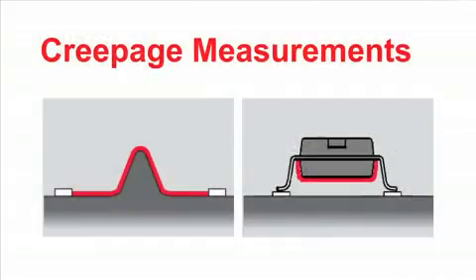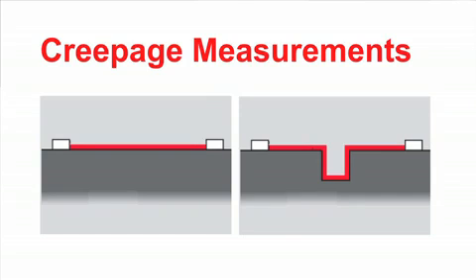Now let's talk about creepage. Creepage is the shortest distance between two uninsulated conductors along the surface of an insulating material. Looking at the diagram, you can see creepage is measured as the shortest distance along the surface between uninsulated conductors. Having enough creepage distance for the voltage level and environment you are designing for will prevent tracking — a breakdown of the insulation material along the surface that creates a conducting path to short across the isolation barrier.